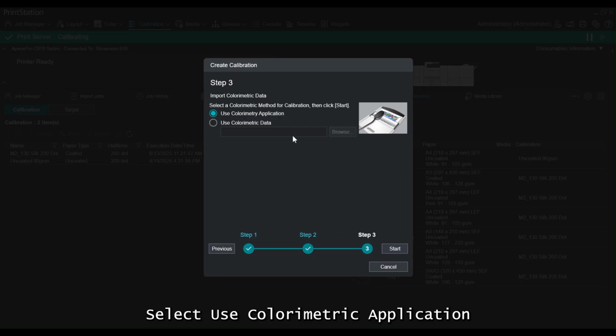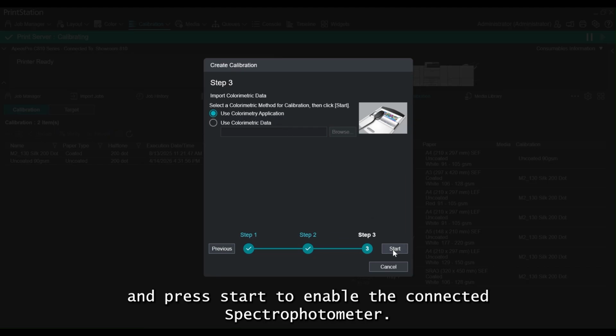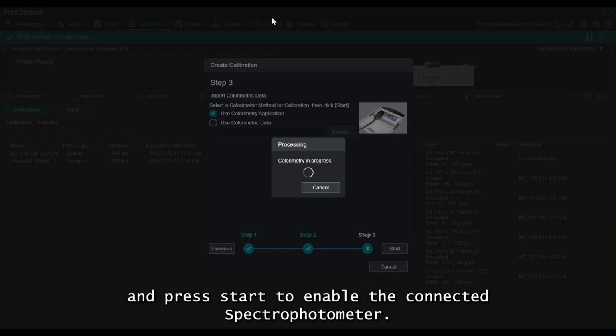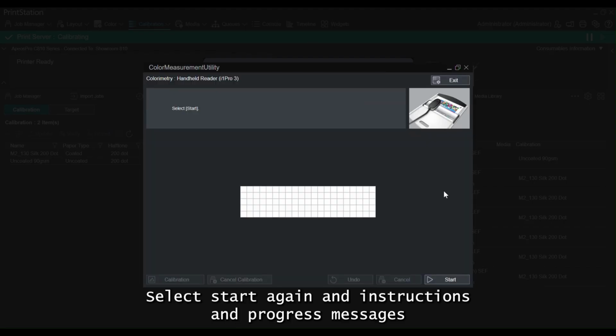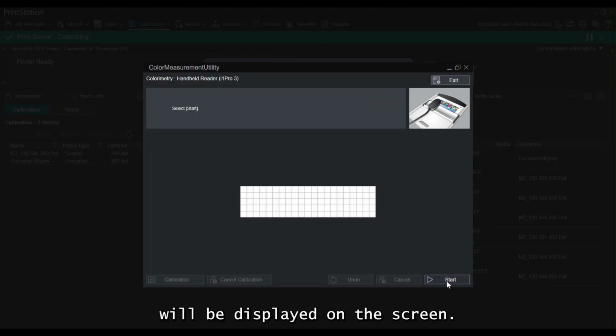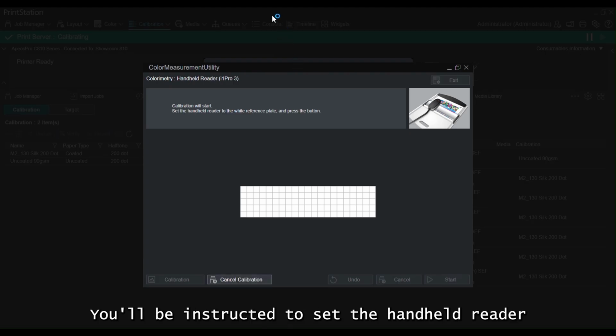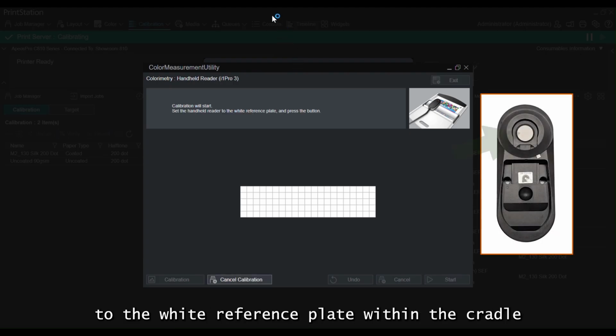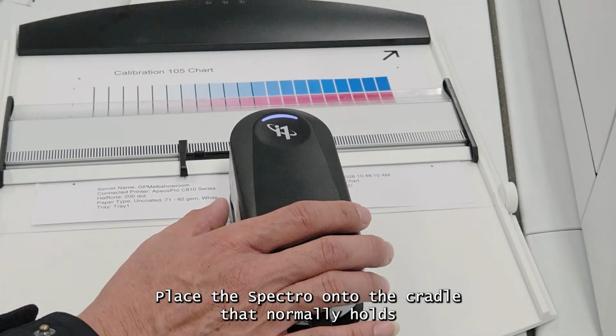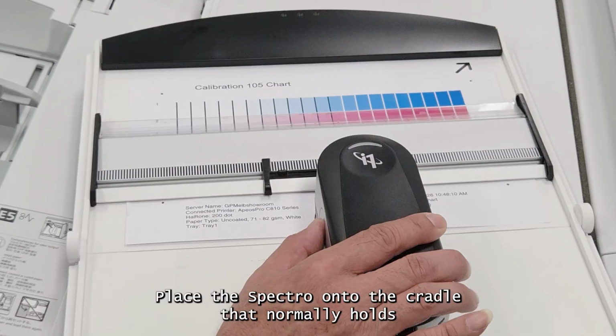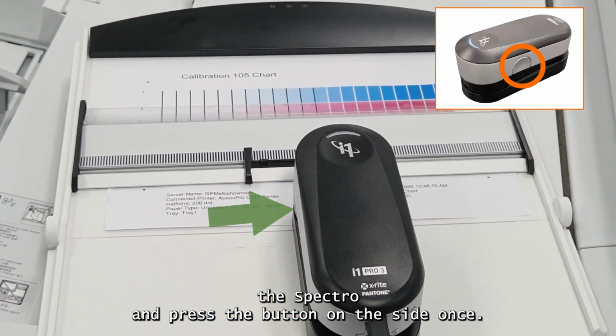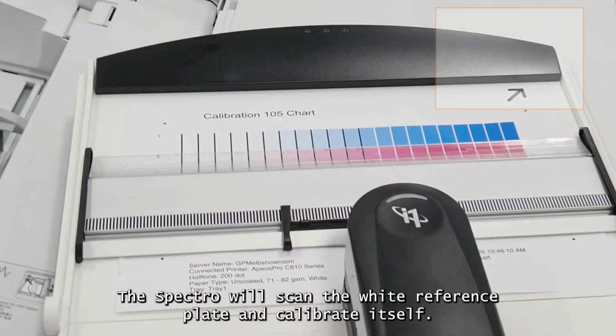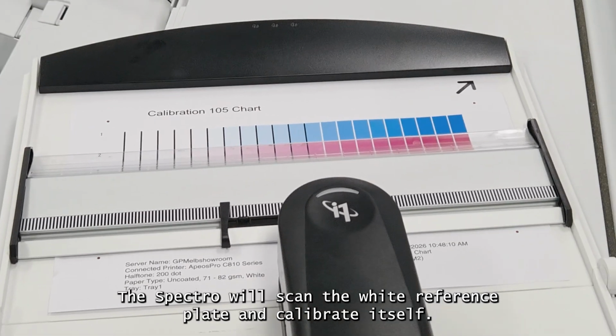Select Use Colorimetry Application and press Start to enable the connected spectrophotometer. Select Start again and instructions and progress messages will be displayed on the screen. You'll be instructed to set the handheld reader to the white reference plate within the cradle and press the button. Place the spectro onto the cradle that normally holds the spectro and press the button on the side once. The spectro will scan the white reference plate and calibrate itself.